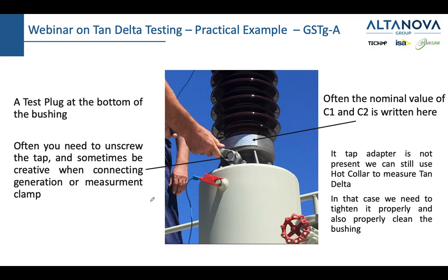If you want to measure the bushing, there is a test plug here, and this test plug needs to be unscrewed, and then you would connect first measurement and later generation here. There are two values you measure on each bushing, C1 and C2. Also, on this nameplate, you would see C1 and C2 written. As my colleague Simone mentioned in the morning, these numbers are the tan delta of the bushing, which was measured in the factory. These numbers can sometimes differ because in the factory, it was not mounted on this particular transformer, so they can be slightly different. And if you do not have this test plug tap, then you can use something which we call the hot collar.